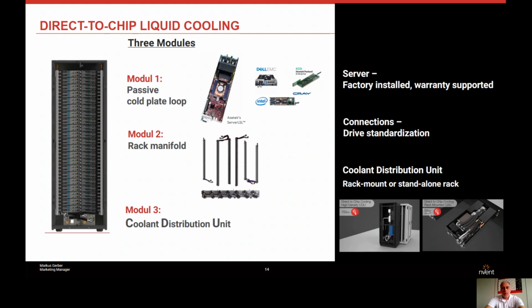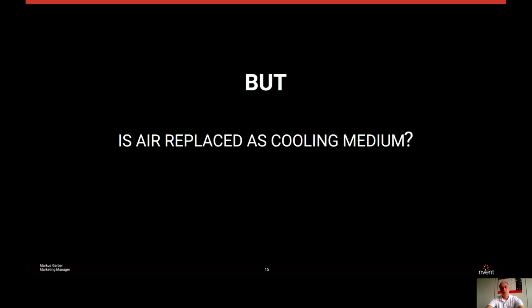Now you could say, okay, highest cooling capacity, servers are available, I don't have to care about warranty, I can drive with very, very high water inlet temperatures. So why is not everyone moving towards direct-to-chip cooling? The main reason is, can it really replace air as a cooling medium? And probably the answer, as you guess, is no. Building up a cold plate that would cool every component inside a server would be very complex. And then we go back to the very first point, which is investment compared to operational costs. From an investment side, it would not make sense.